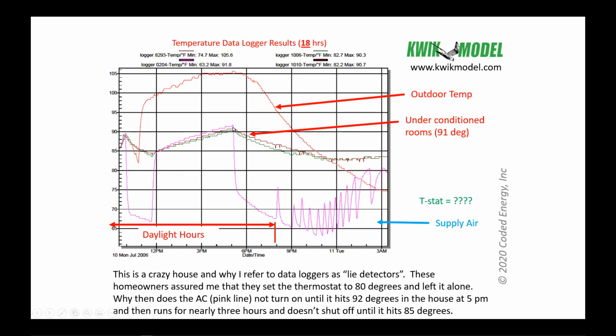And now the air conditioner drops down and look how long it runs for. It runs from 5 o'clock till almost 8 o'clock at night. It runs for 3 hours straight. That's this big, long drop here. Now, another interesting thing is to look at the supply temperatures in the first hour. When it turns on at 5 o'clock, the supply temperature drops to here. And the longer it runs, the colder that supply air temperature gets.